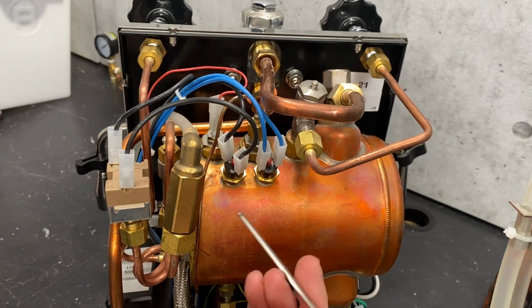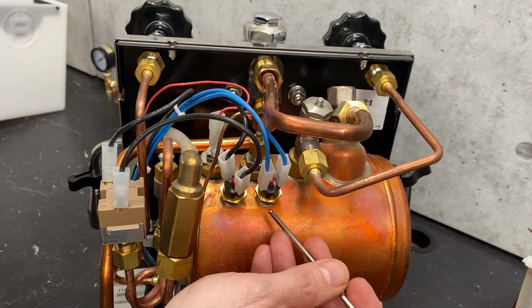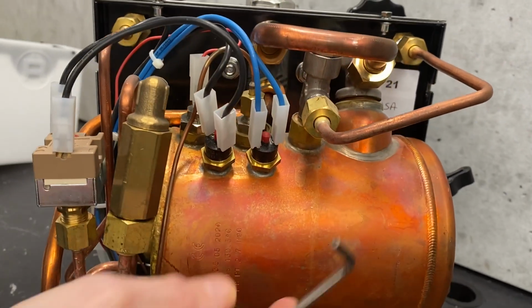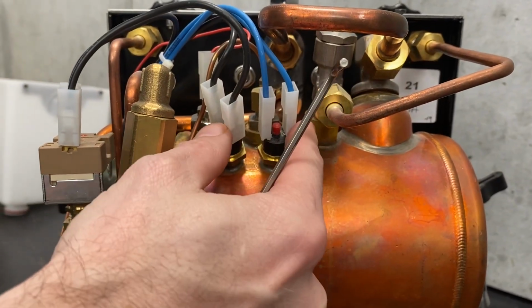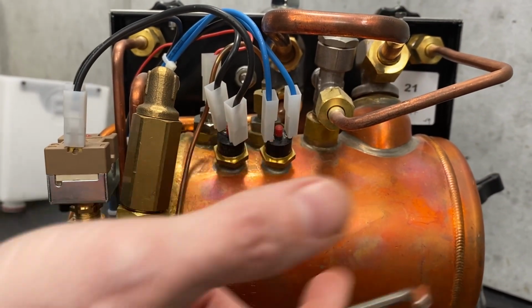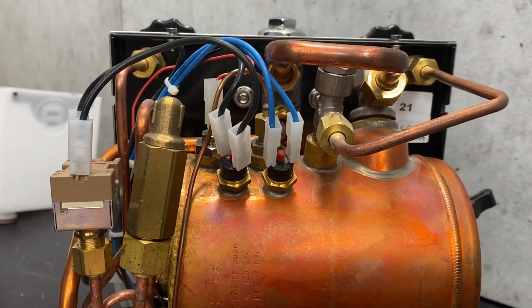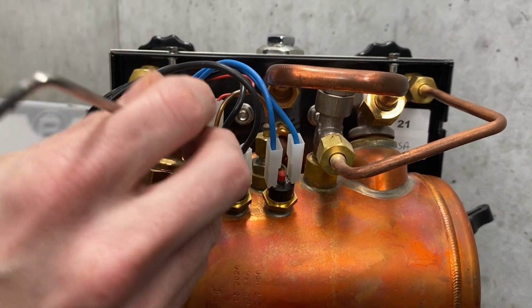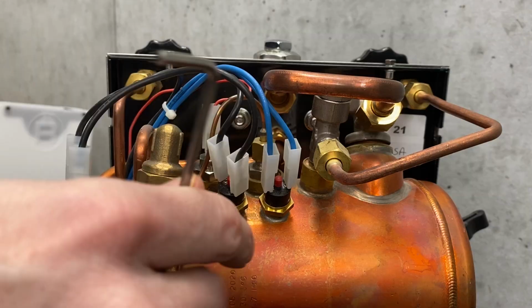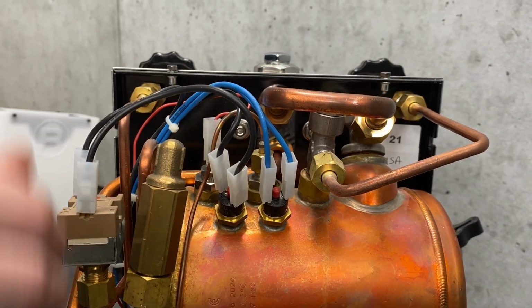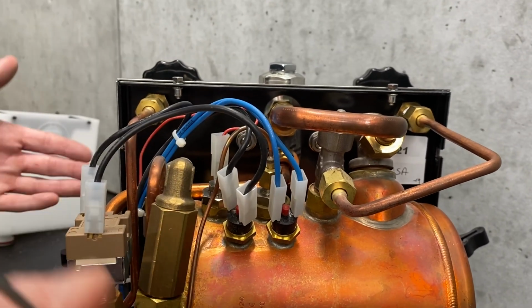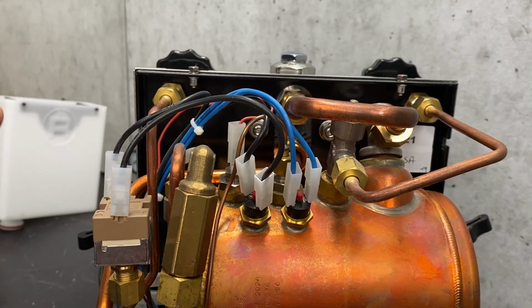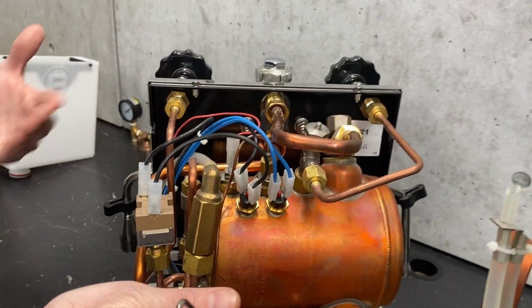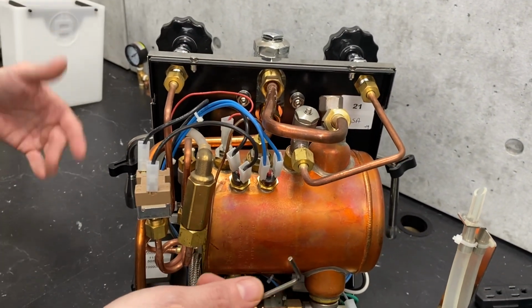Exactly, yep. And these are thermal, so it's based on if this boiler starts overheating, that is when it would trip one of these. It is possible for them to just fail over time. Not as common, usually there is an underlying reason, but if you do ever have to reset one of these limits, I always suggest keeping an eye on the machine. Don't let the machine stay idle without you around until you've had a chance to make sure everything's working fine for at least a few days.